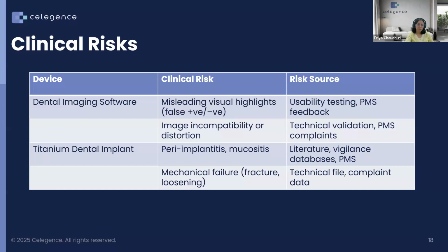And then the CER should document that rate and assess how the device compares, based on the clinical data of the device. So whether it's aligned with the state of the art from similar devices or the best practices from the papers that we are supposed to find, and if the design or labeling mitigates the risk to a reasonable level. That's the ultimate aim of the clinical evaluation.